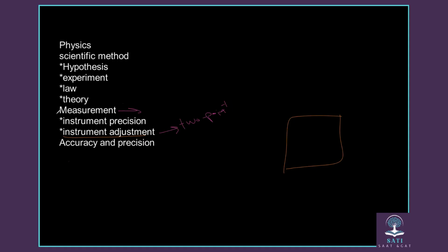So first point here, I take a mass that is, for example, 5 kilograms, and I know it. So this is a known quantity. It is 5 kilograms. And I put it here, and I make sure it gives me also 5 kilograms. Okay, now I made sure here for the first point, it gives me right readings.